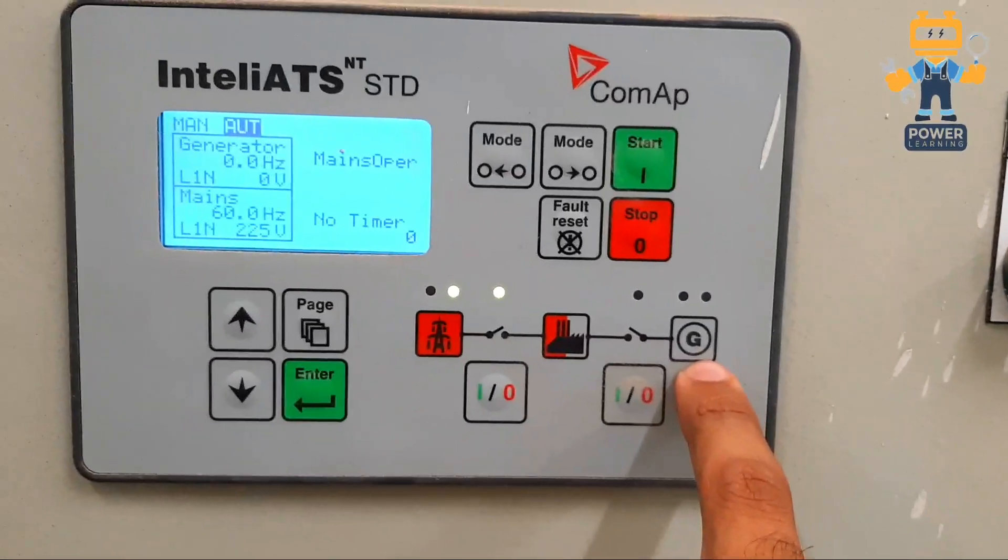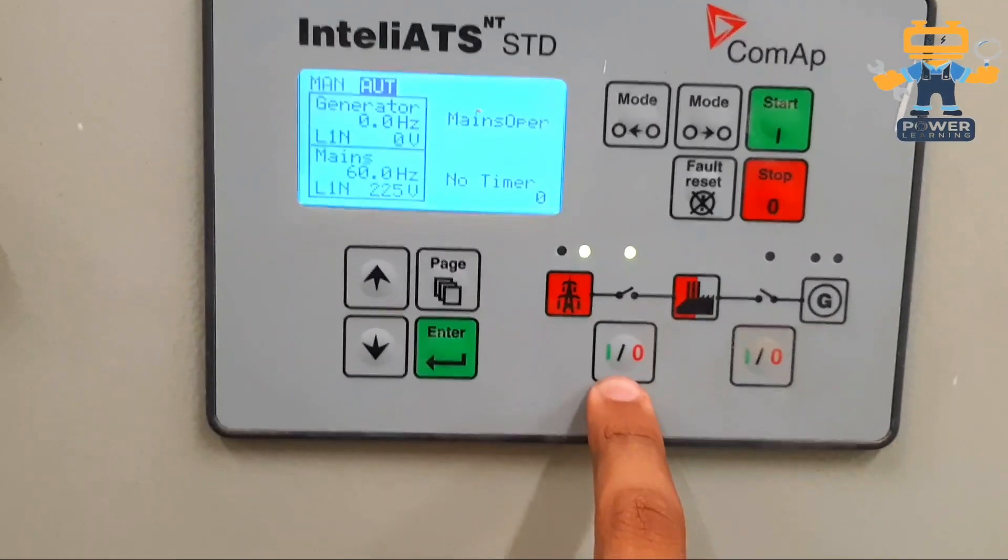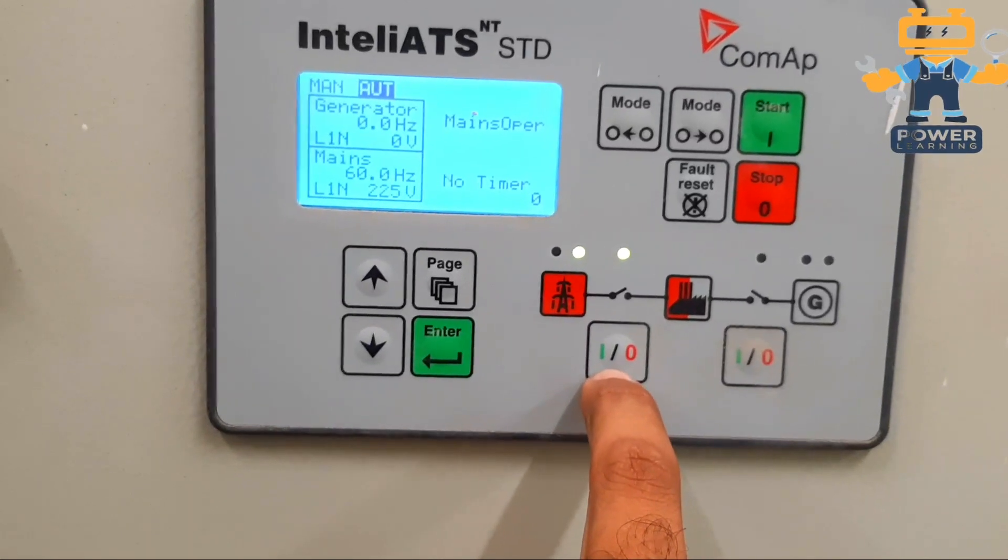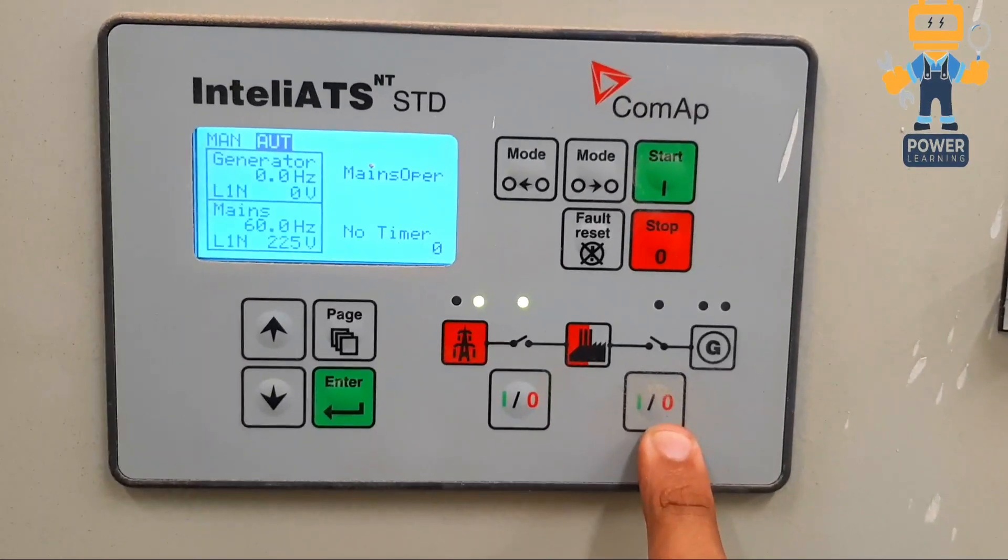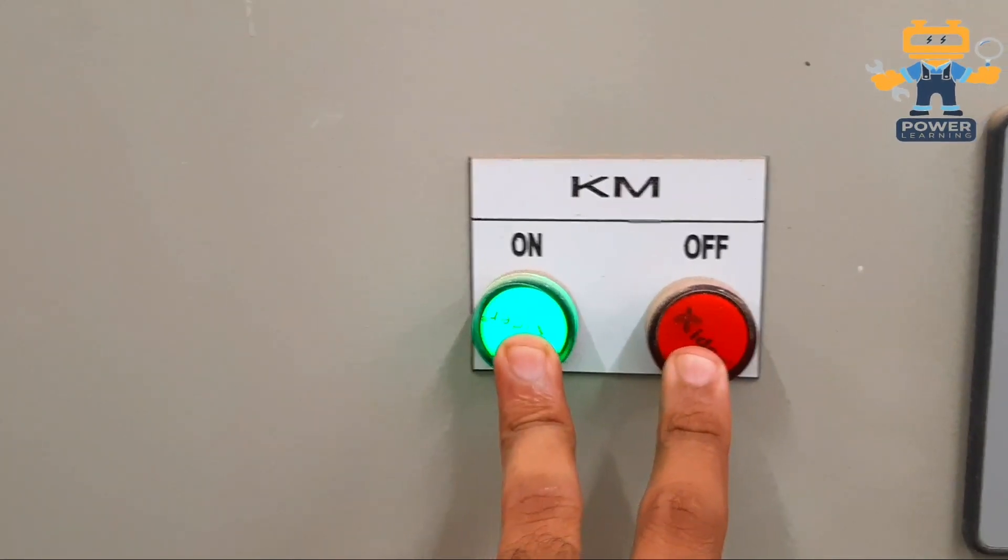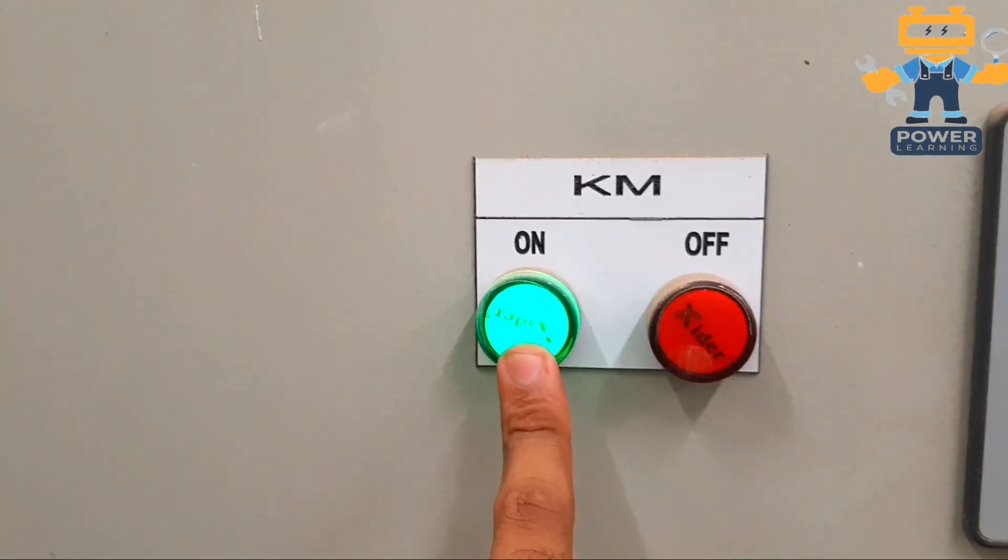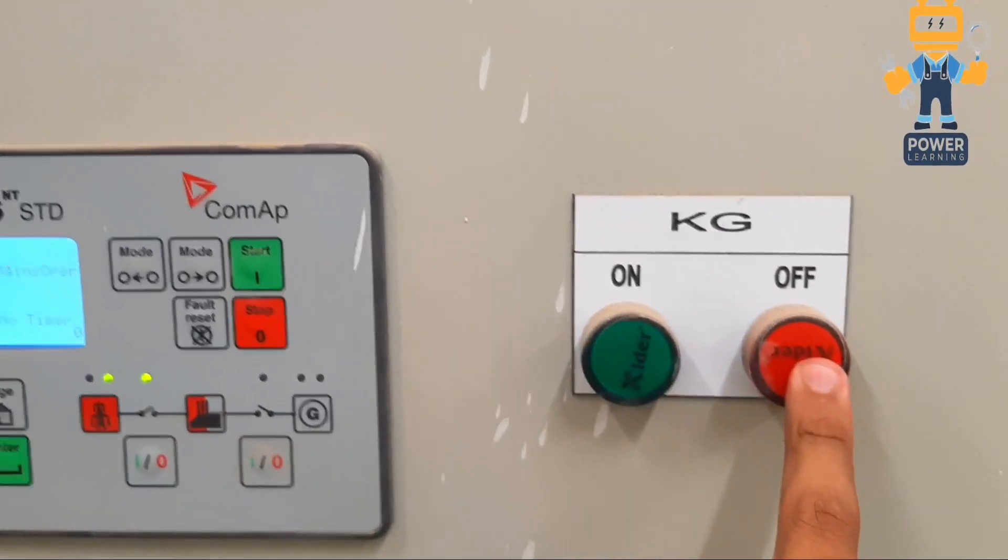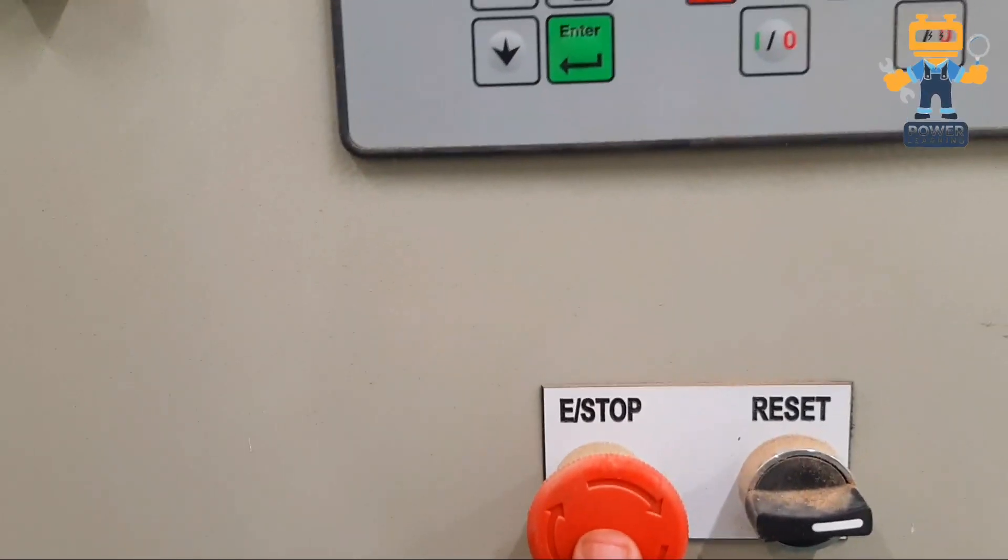Here we have load, here we have generator. This is a manual push button for turning on mains breaker, and this is for manual push button for turning on generator breaker. We have two indications. These two indications show the main supply. Now the main supply is on and there is no alarm. Generator is completely off, so there is no indication. This is our emergency stop push button and this is the reset push button.